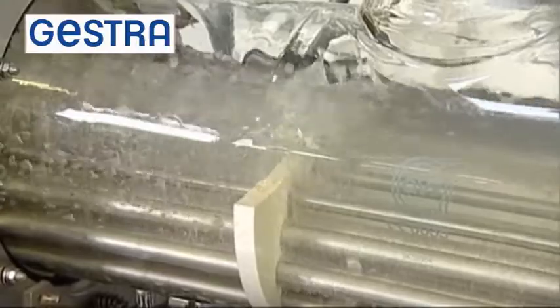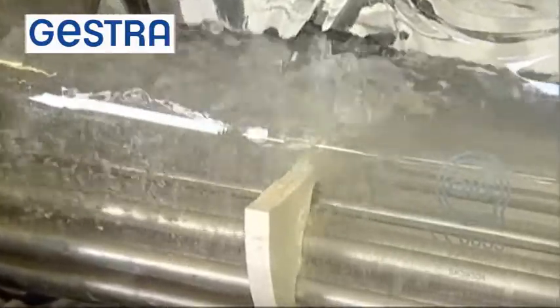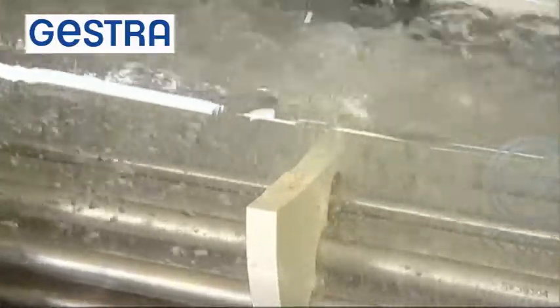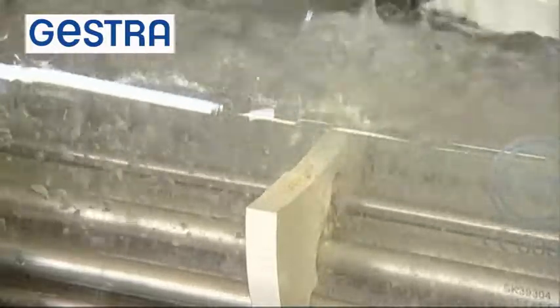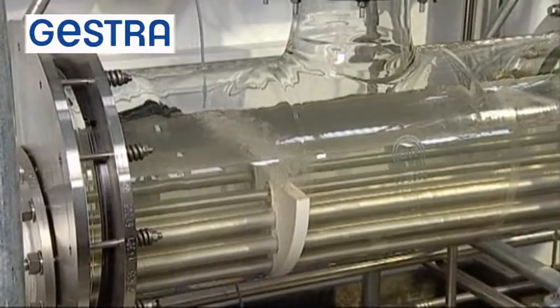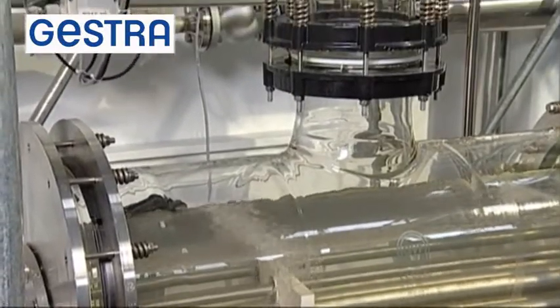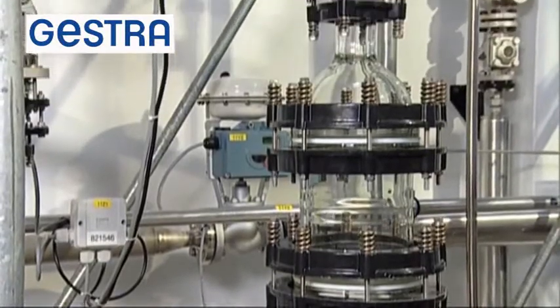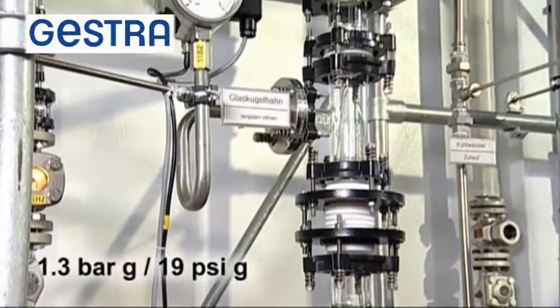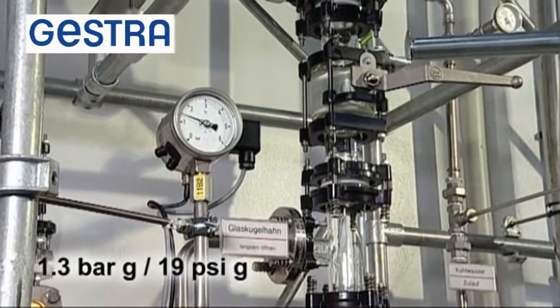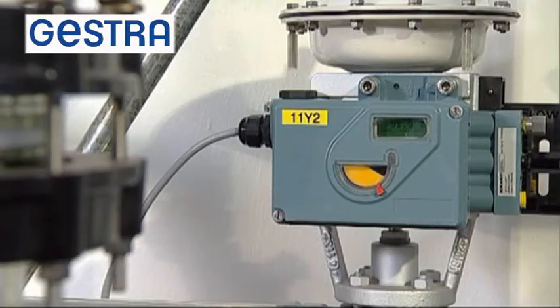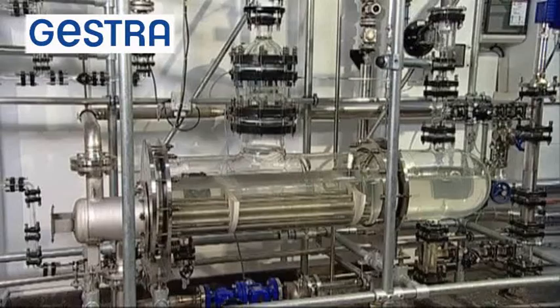When the boiling point is exceeded near the heating rods and their PTFE supports, the first steam bubbles in the water occur there. Initially, they collapse almost immediately, but as the heating period increases, they manage to rise up into the steam space above the water surface until the boiling point has also been reached there. Because steam has 1700 times the volume of its equivalent as water, the pressure increases within the steam generator. The operating pressure is regulated to 1.3 bar gauge, so that the pressure transducer acts through the pressure controller to close the pneumatic control valve. This throttles the steam supply in the evaporator head.